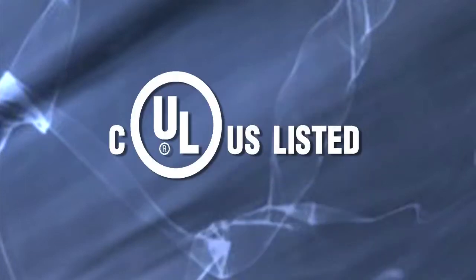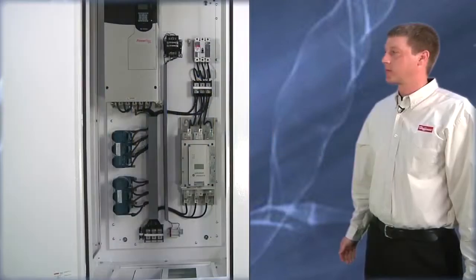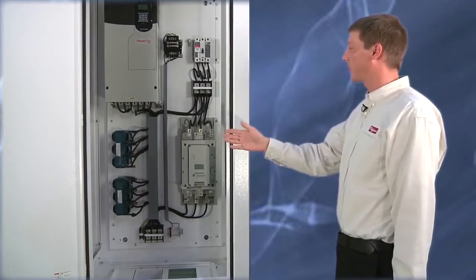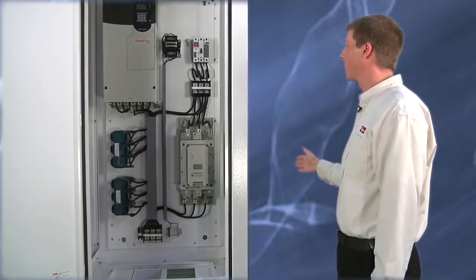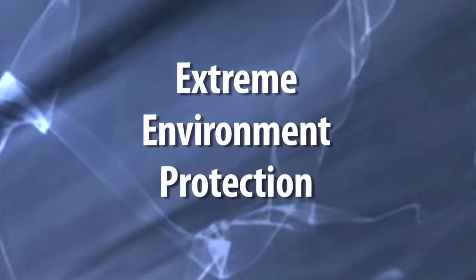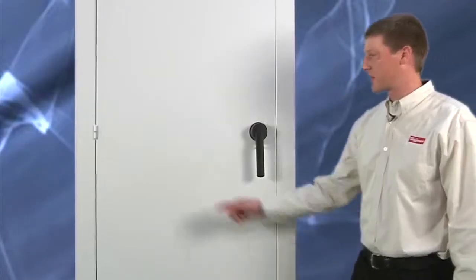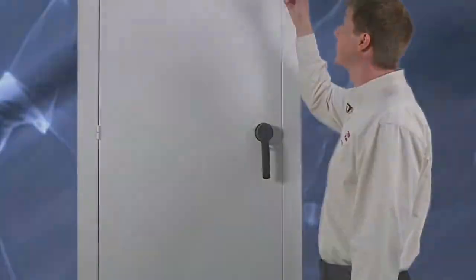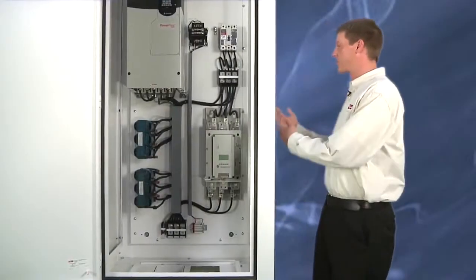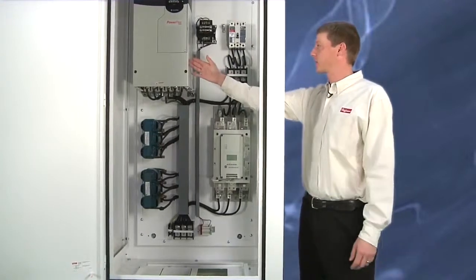The Weatherflow HD enclosure was tested vigorously in our UL certified lab. We load tested the two-door version with 2,000 pounds on the left-hand panel and 400 pounds on the right-hand panel, and saw no distortion. This cabinet is rated NEMA 3R. It features stainless steel hinge pins and stainless steel mesh to hold up to harsh environments. The modular design lets you remove the side covers and gain easy access to the controls.